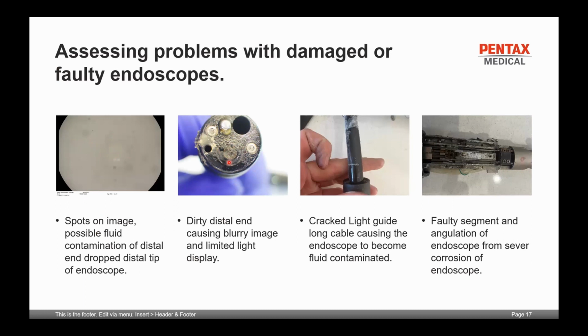Sometimes after the endoscope has been reprocessed, they will hang the endoscope up. Once the endoscope is hanging up, the nozzles might still have some form of a fluid or even contamination to it that will be dripping out over the lens. And the next day, or it sits overnight, and the next day they want to start the cases or the procedures, and they're complaining of a blurry image or a light that's not being emitted correctly. Have a look to make sure that the distal end is nice and clear.